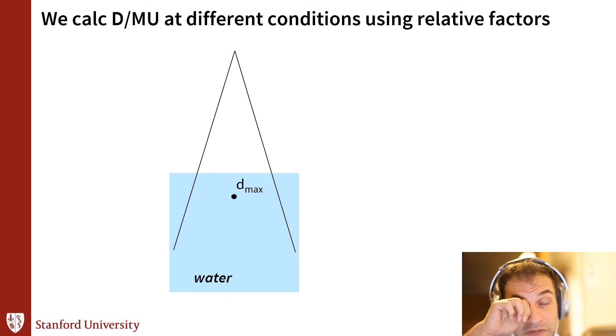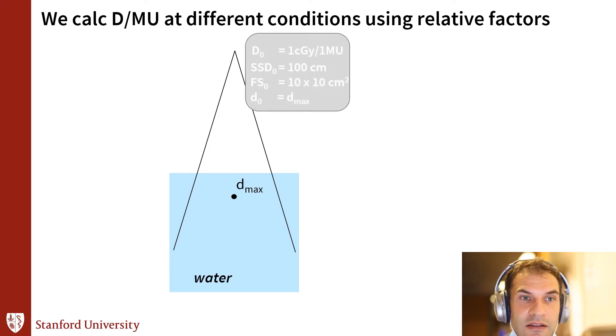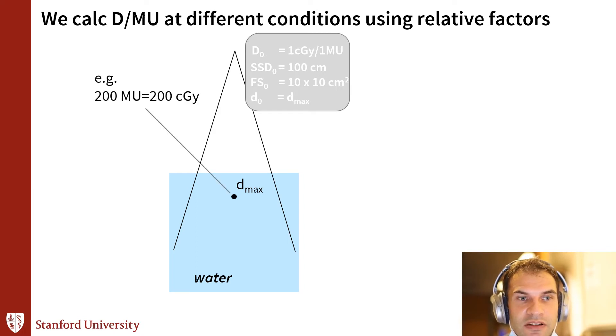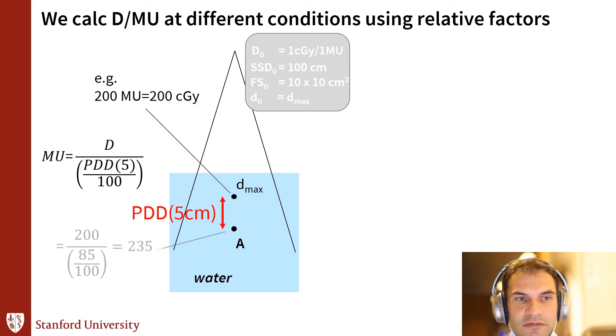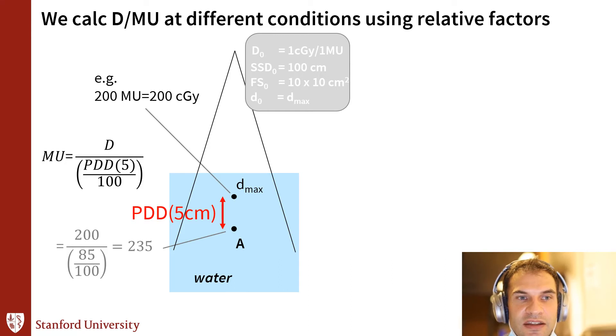We calculate dose per MU for different conditions using relative factors. If we have a point at our calibration condition, 200 MU gives 200 centigray. Then we want to calculate the dose 5 cm deeper — all we're doing is changing the depth. We move down the PDD curve, find that the PDD for 5 cm depth is 85%, so 200 divided by 0.85 gives 235 monitor units needed to deliver 200 centigray at 5 cm depth.